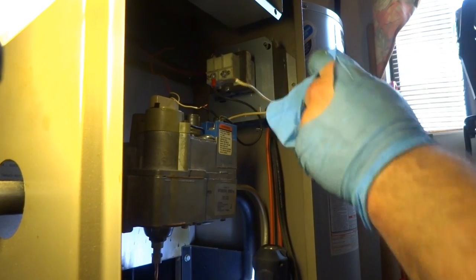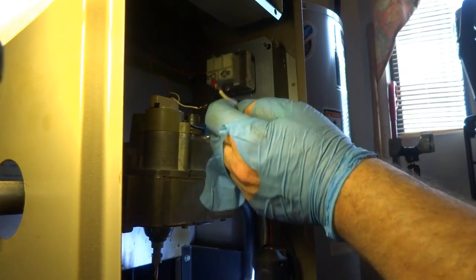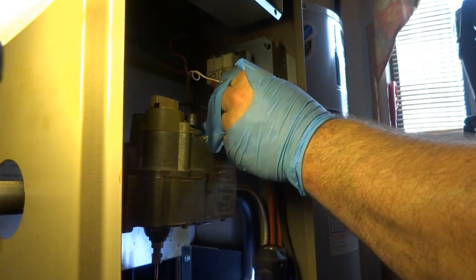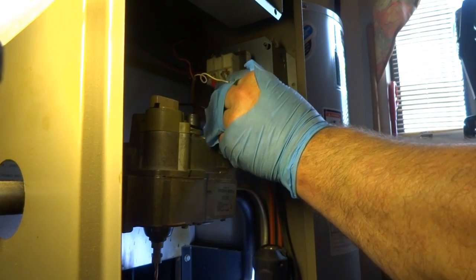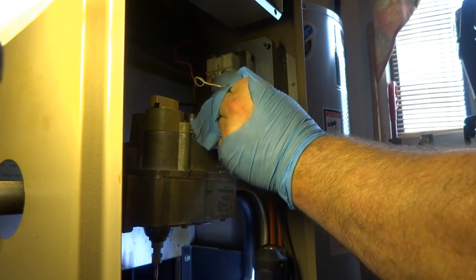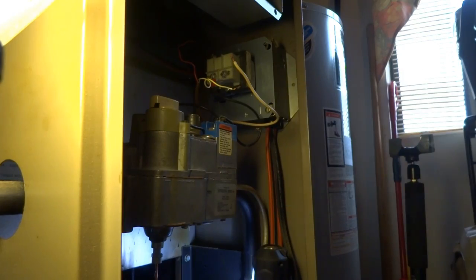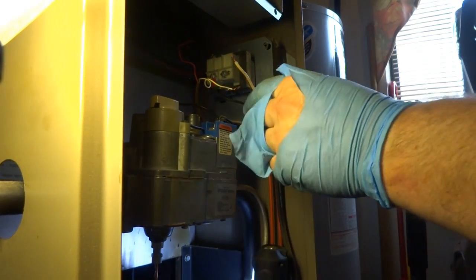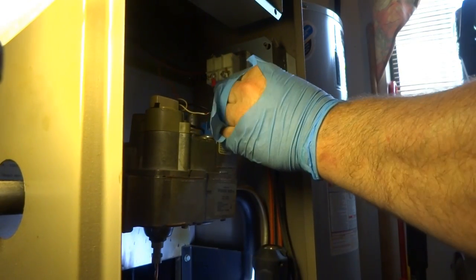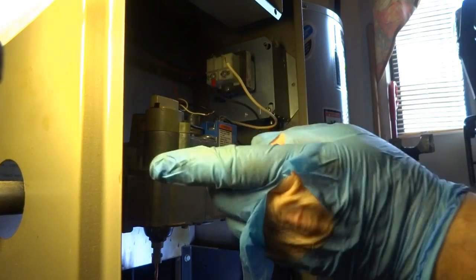I got the transformer changed, so now I got power, and I'm jumping out the thermostat. Listen to it, hear it click? The gas valve's not letting any gas through. We got a bad gas valve, too. Hear it? Hear it clicking? Yeah, that should let the gas through, because I'm on, right?